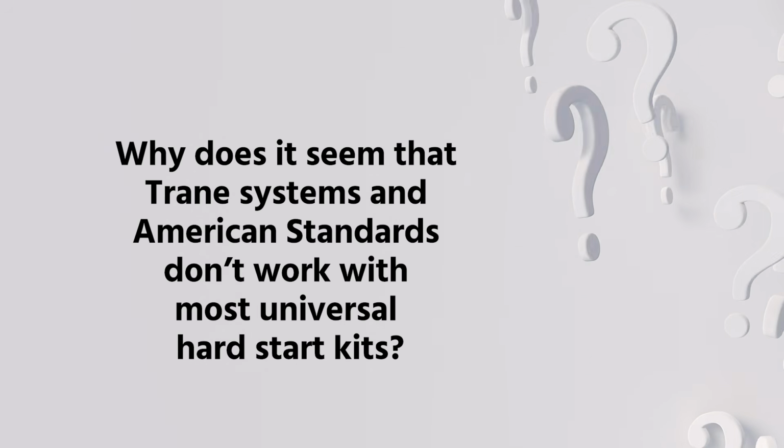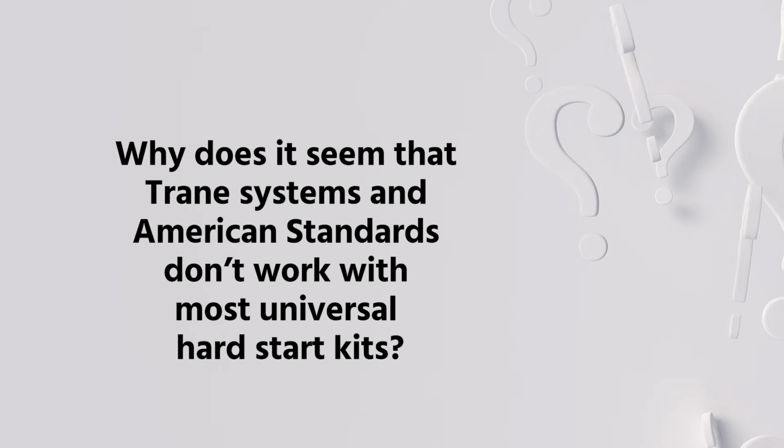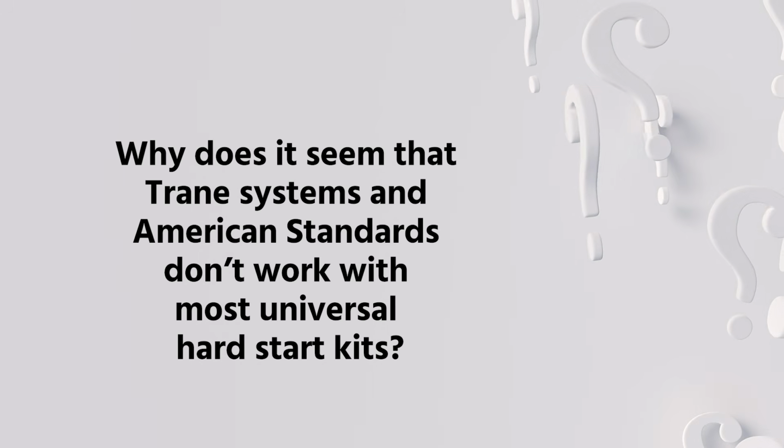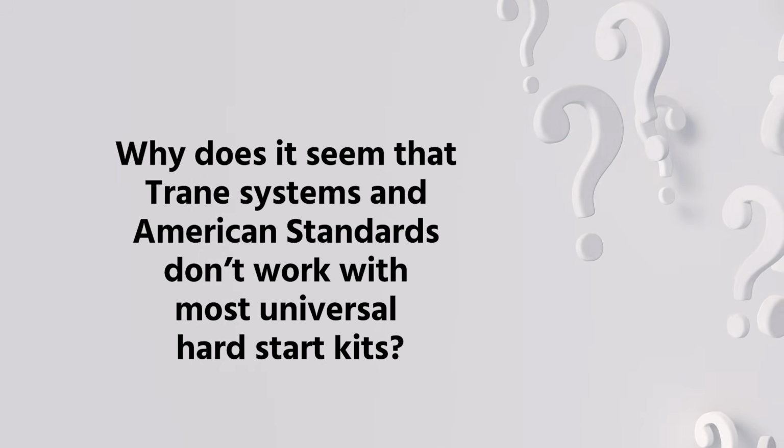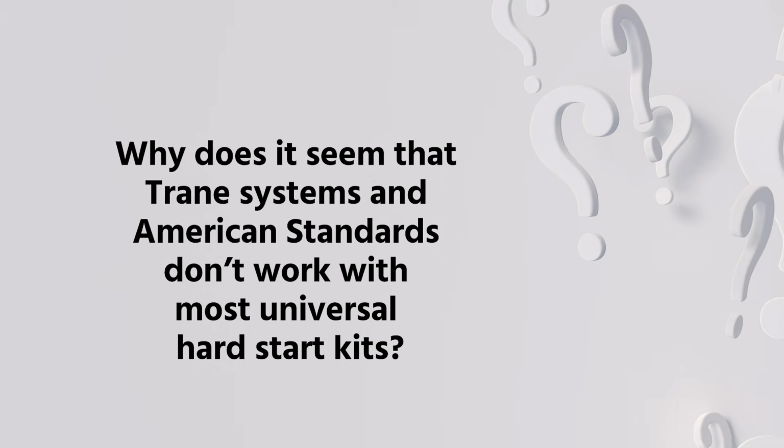We're not going to waste a customer's money to go back and put in a factory hard start if the thing's 10, 11, 12, 13 years old. Why does it seem that Trane systems and American Standard don't work with most universal hard start kits? And this comes down to the fact that they require a significantly different capacitance and a significantly different potential relay. It's just that they need more.